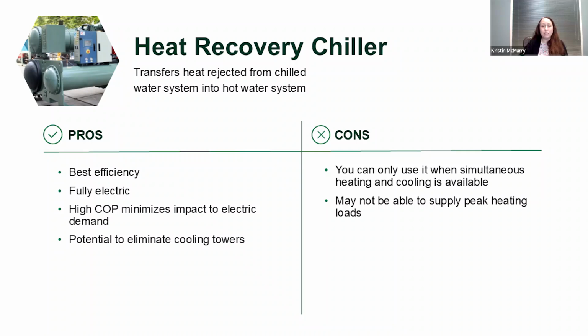But again, you can only use it for simultaneous heating and cooling, and if you're not the right client for this, it might not be able to supply your peak heating loads, because generally your peak heating load does not happen at the same time as your peak cooling load - that would be pretty surprising. If your cooling load isn't sufficient to supply the heating load, you're going to need something else to supplement it.